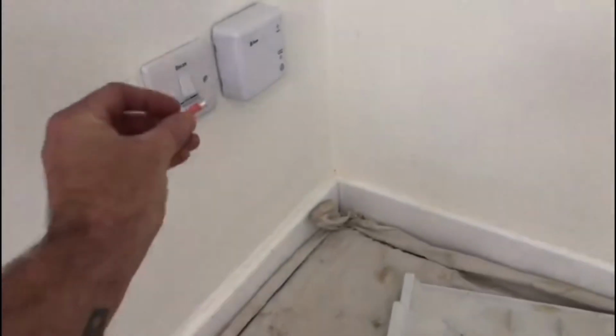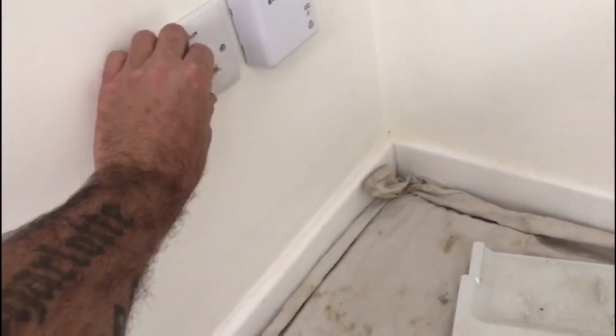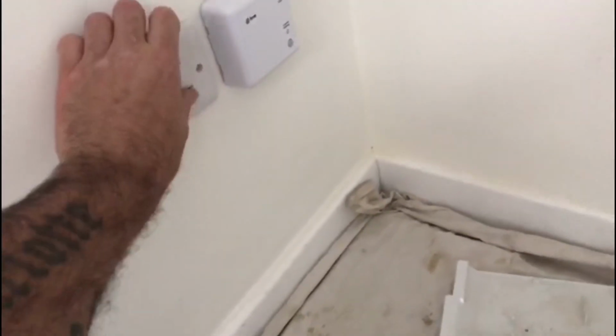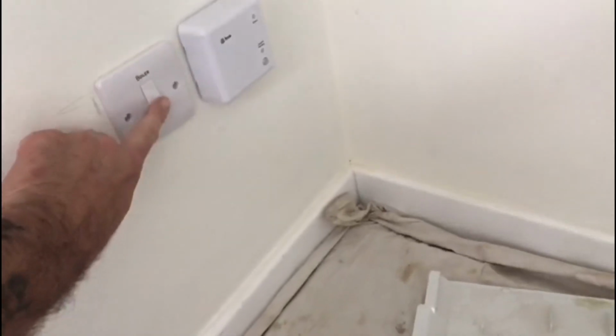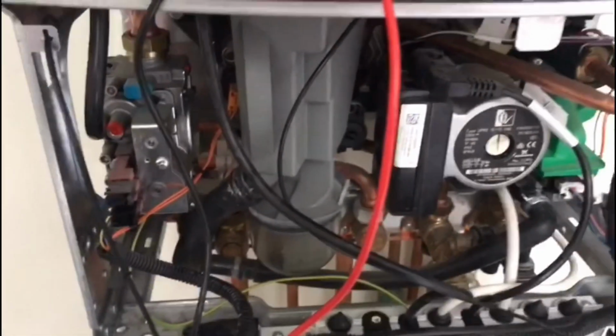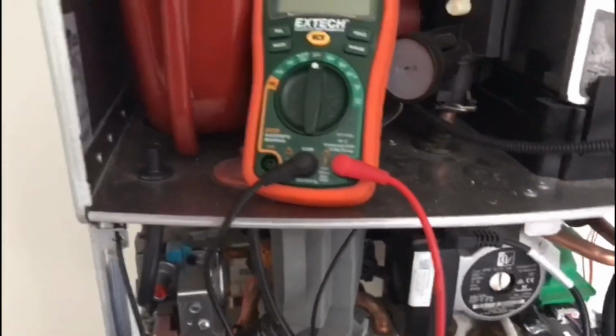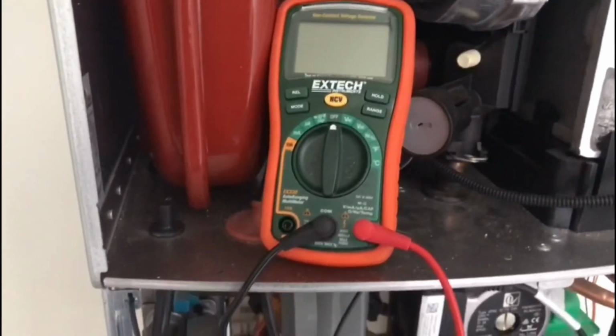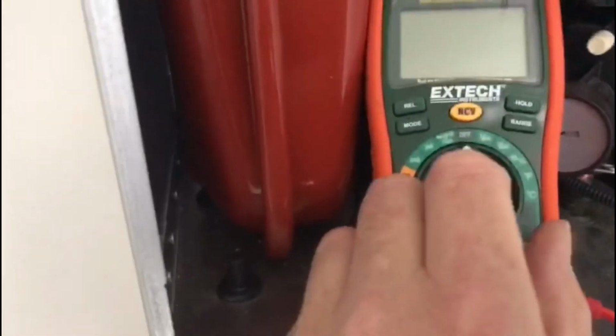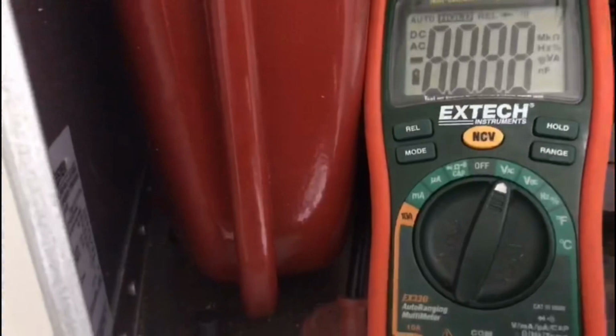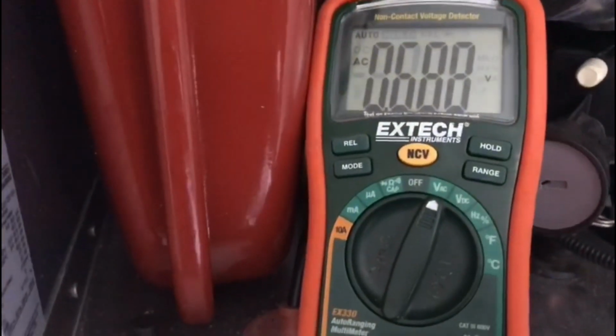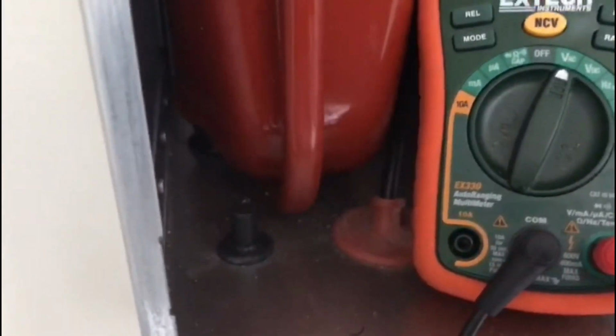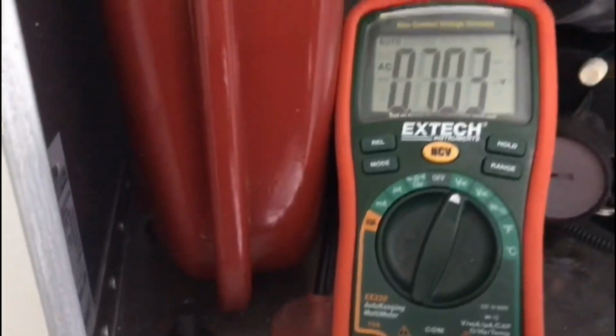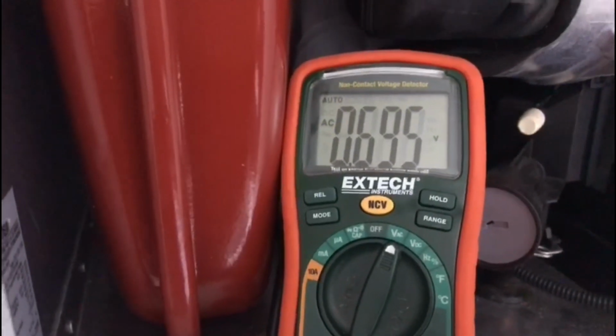What you do, you put your fuse back into your fuse connection unit, shut that off, turn the boiler on. Boiler's in operation. Now, because I've only got one hand free really, you put your tester onto voltage alternating current, because in this country we use alternating current, so you test at alternating current.